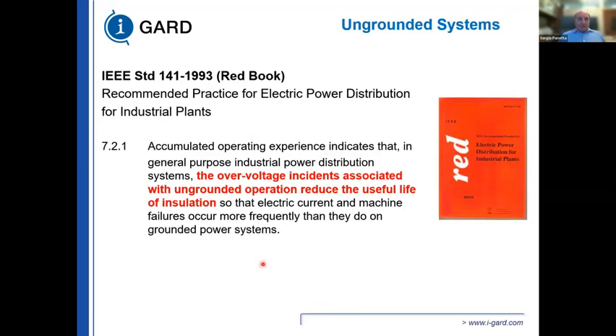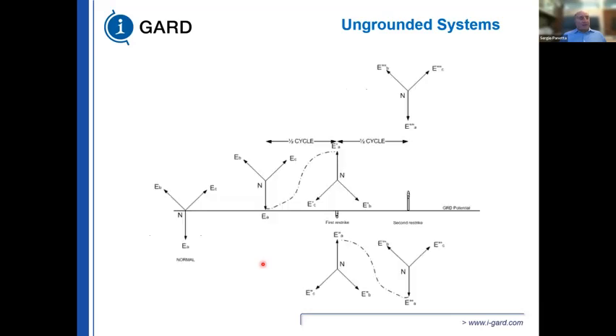The Red Book, IEEE Standard 141, says that overvoltage incidences associated with ungrounded operation reduce the useful life of insulation. Air is an insulation, right? So if you stress the air, you're going to weaken the insulation, and if you have a ground fault, chances are you have a little bit of arcing and it deteriorates the insulation. The overvoltage is explained in Beeman's book. This is an example right out of Beeman's book.